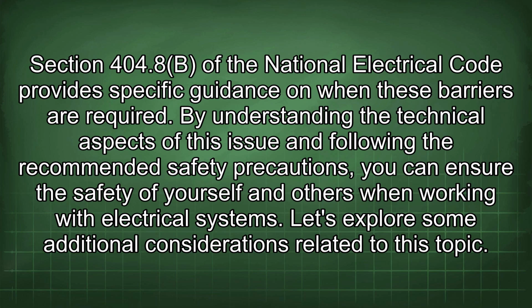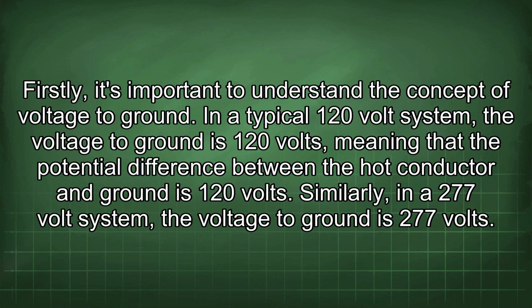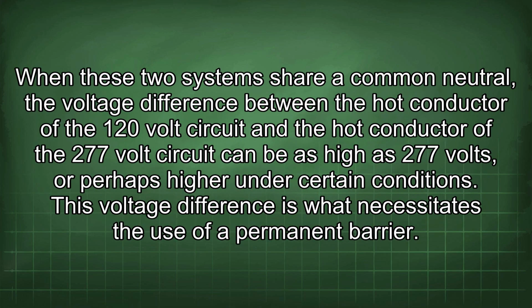Let's explore some additional considerations related to this topic. Firstly, it's important to understand the concept of voltage to ground. In a typical 120 volt system, the voltage to ground is 120 volts, meaning that the potential difference between the hot conductor and ground is 120 volts. Similarly, in a 277 volt system, the voltage to ground is 277 volts. When these two systems share a common neutral, the voltage difference between the hot conductor of the 120 volt circuit and the hot conductor of the 277 volt circuit can be as high as 277 volts, or perhaps higher under certain conditions. This voltage difference is what necessitates the use of a permanent barrier.